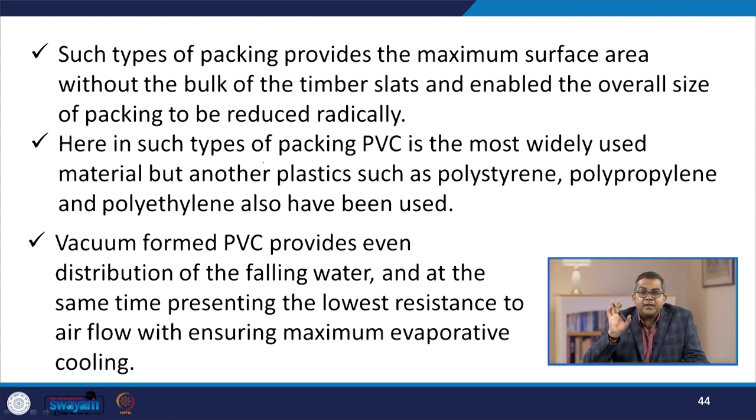Such type of packing provides the maximum surface area without the bulk of the timber slats, and enables the overall size of packing to be reduced radically. In such packing, PVC is the most widely used material, but other plastics like polystyrene, polypropylene, polyethylene have also been used. Vacuum formed polyvinyl chloride provides even distribution of the falling film, and at the same time presents the lowest resistance to airflow while ensuring maximum evaporative cooling.